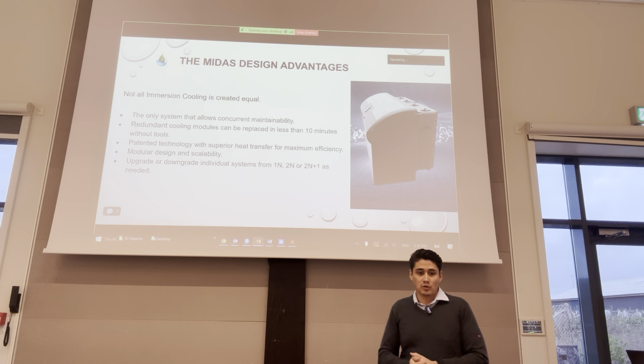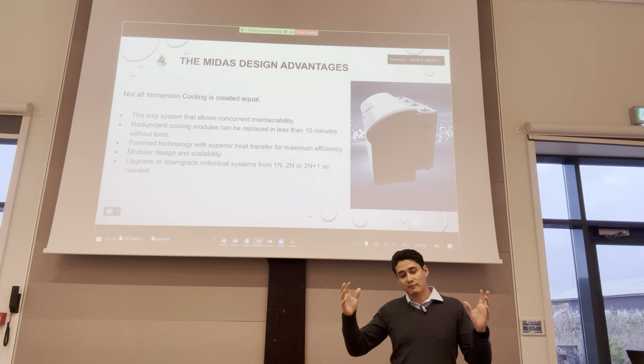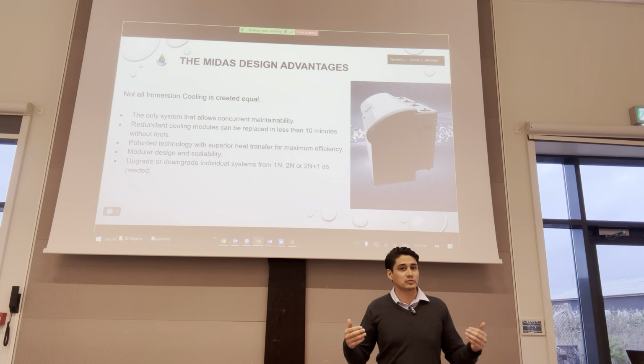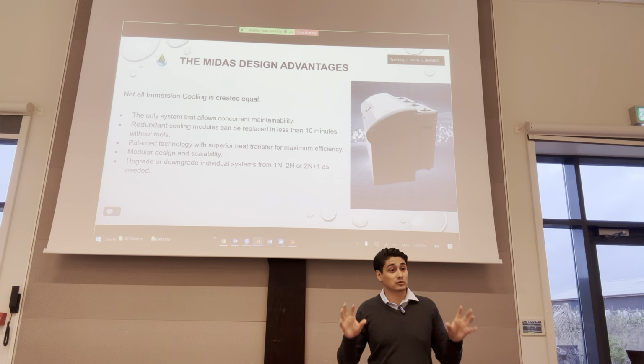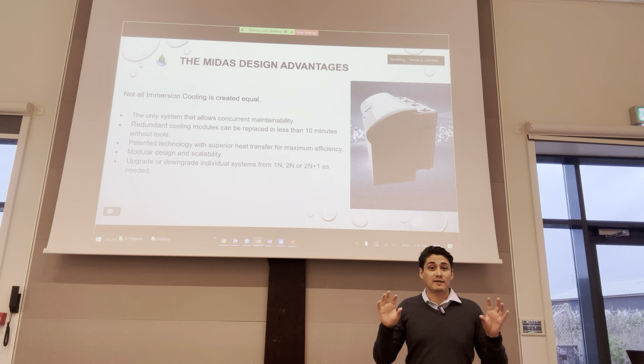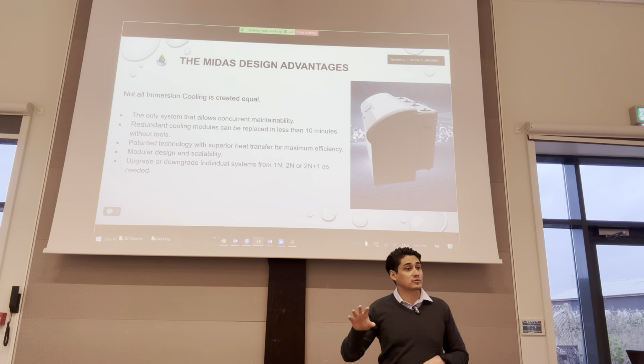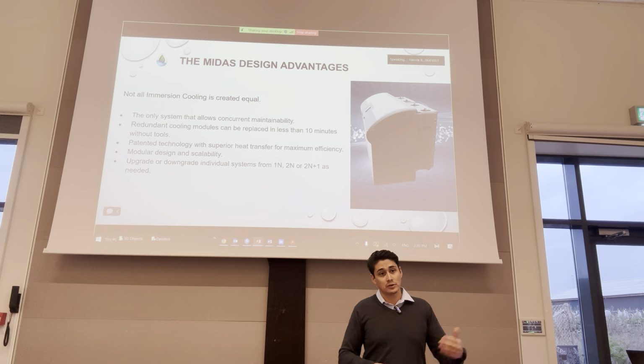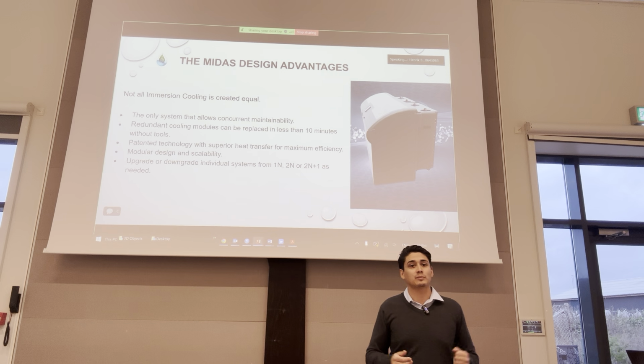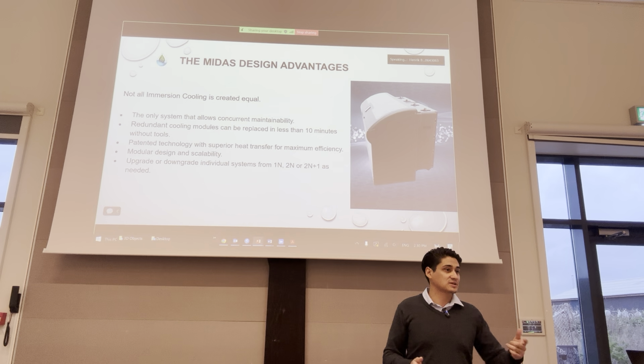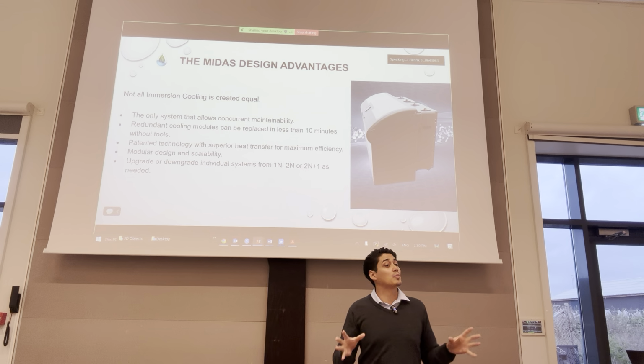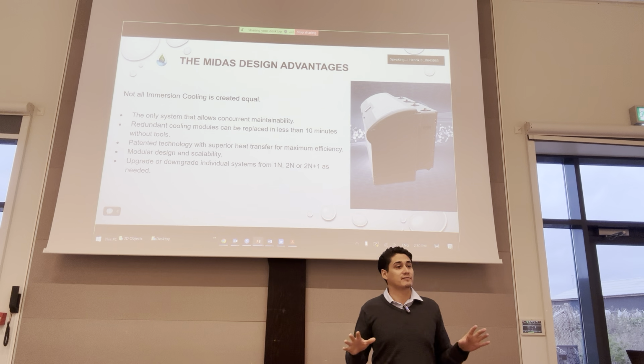Going to our system specifically, we have one tank and the CDU, cooling distribution units. We put two of those in the back, so they're fully redundant. We have them hot swappable, so if one is running and the other goes down, you can take that out, and an untrained person in less than 10 minutes can take one out, put one in, and go back to full redundancy without anything ever noticing.